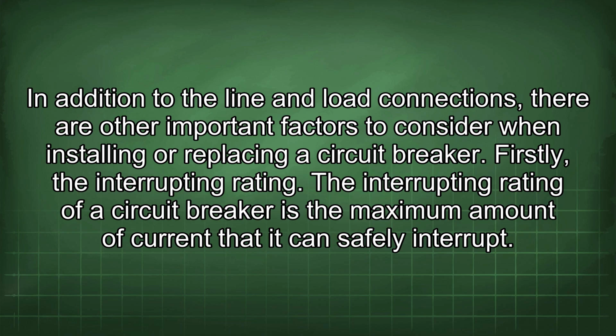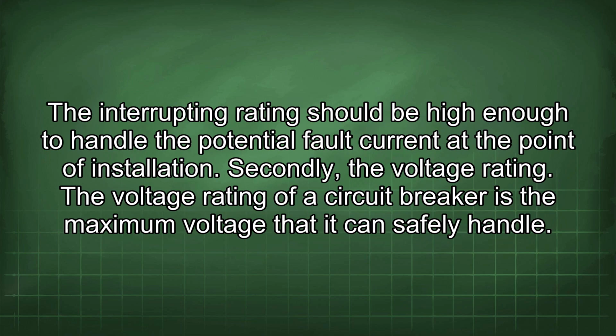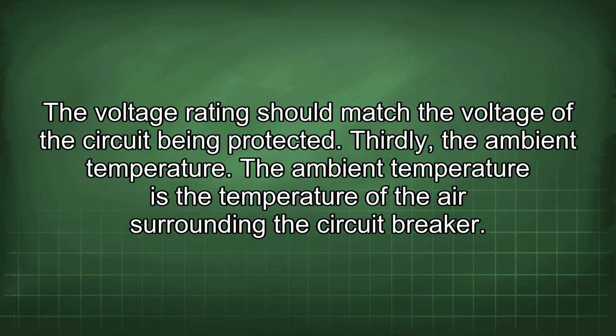In addition to the line and load connections, there are other important factors to consider when installing or replacing a circuit breaker. Firstly, the interrupting rating. The interrupting rating of a circuit breaker is the maximum amount of current that it can safely interrupt. The interrupting rating should be high enough to handle the potential fault current at the point of installation. Secondly, the voltage rating. The voltage rating of a circuit breaker is the maximum voltage that it can safely handle. The voltage rating should match the voltage of the circuit being protected.